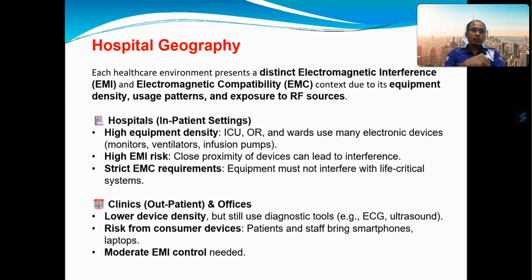Now we look at the high EMI risk. The close proximity of the devices, for example the monitors, ventilators, and also the infusion pumps, can lead to interference.